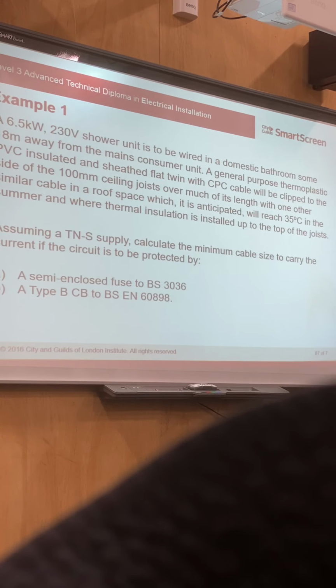Okay. So there's 2 there. It says 2. Remember, it's in the wording here. It will catch people out because they like to do this in all the exams. It's with one other similar cable in the roof. That's the hint that it's there with one other circuit. So you're now no longer looking at one circuit there, you're now looking at 2 circuits. What did you say? 0.8?